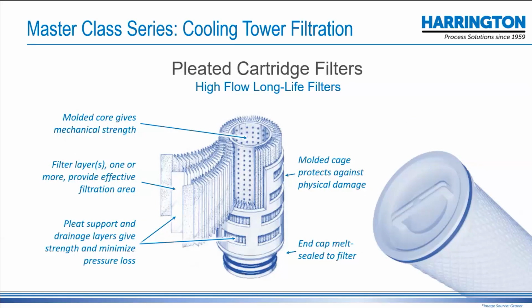Then there are pleated filters. Of course, the high flows would be a pleated, and they come in different materials, different porosities, different lengths. Very, very popular in process cooling water loops. So I would imagine that you would see a pleated filter quite often in one of these applications. And that's fine if they're in the 1, 5, or perhaps 10 micron range. That's a good solution.